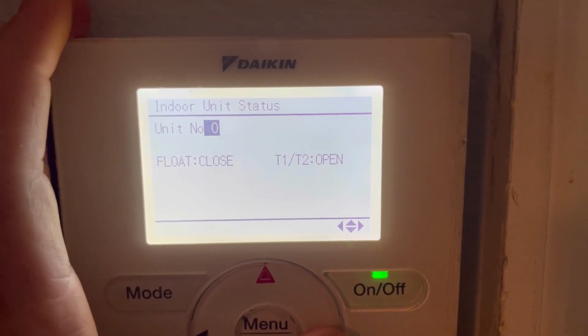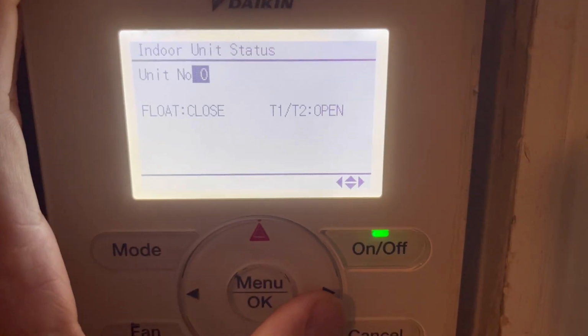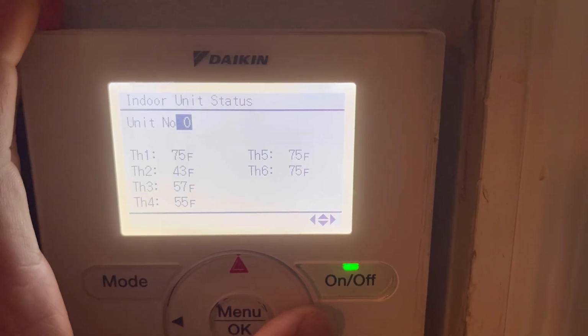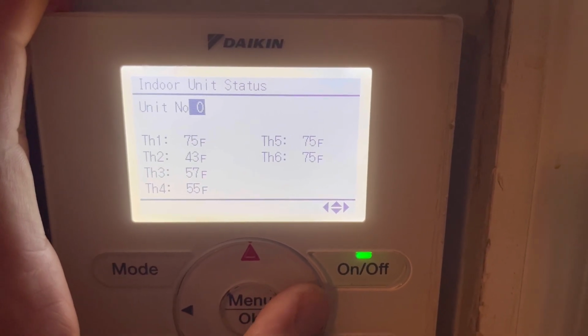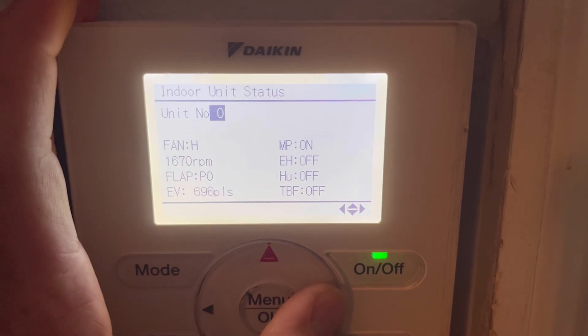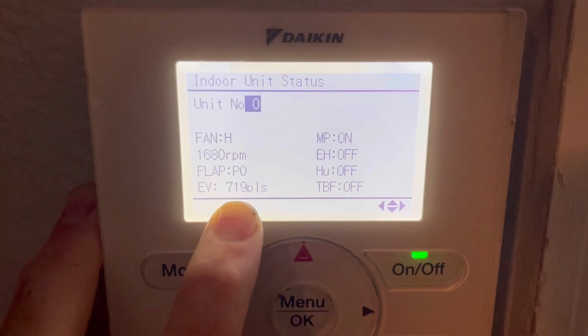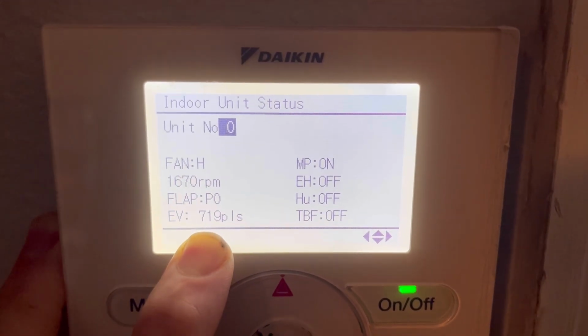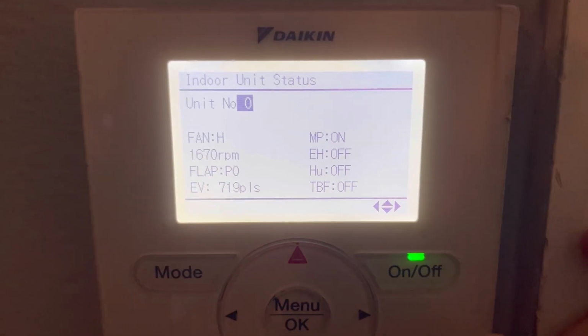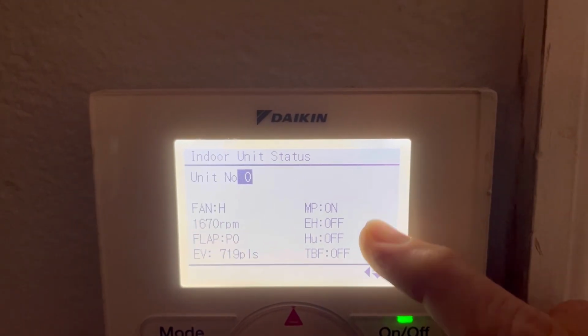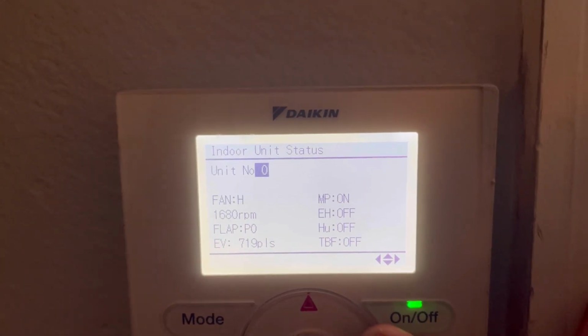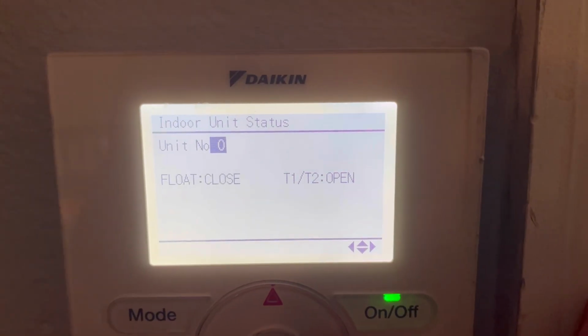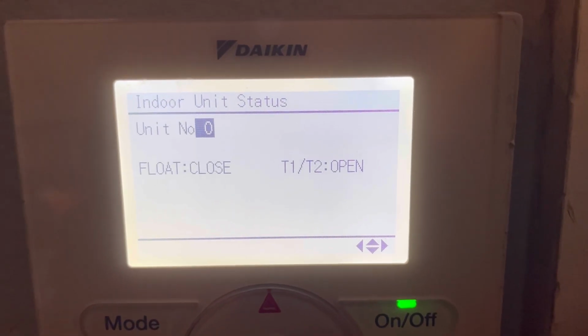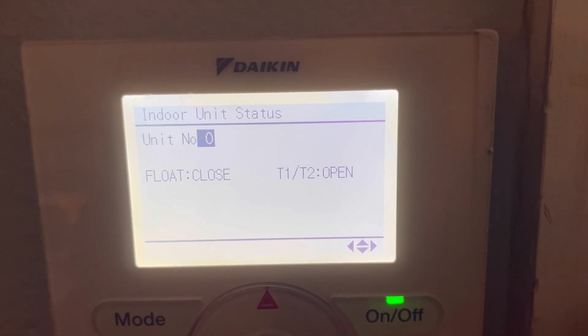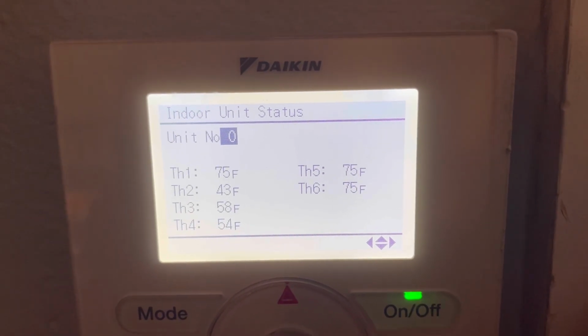I hit the right arrow, my float switch is closed, my T1, T2 is open, and then my sensors are at the end. So I have 3 menus here in maintenance menu, right? I can actually watch my valve pulses change over time, which is extremely valuable. And I can also confirm all the accessories that might be hooked up, what's opening, what's closing, what's running, what's not. If my T1, T2 is open, if my float switch is tripped, all that stuff is here at the maintenance menu, and it's constantly changing.